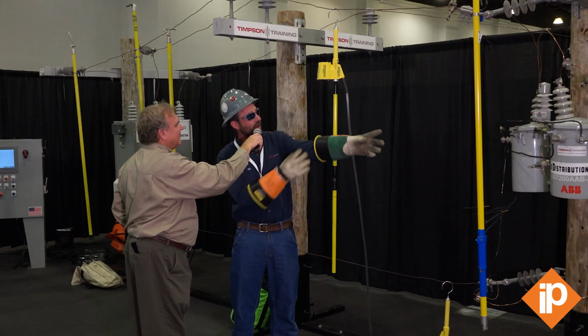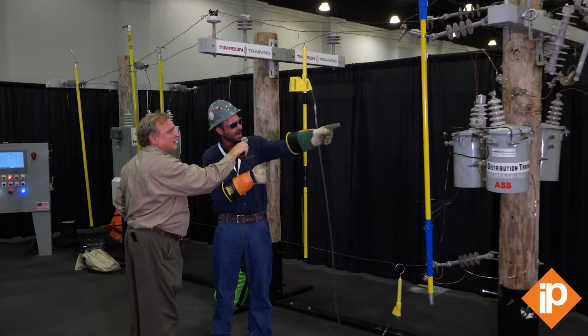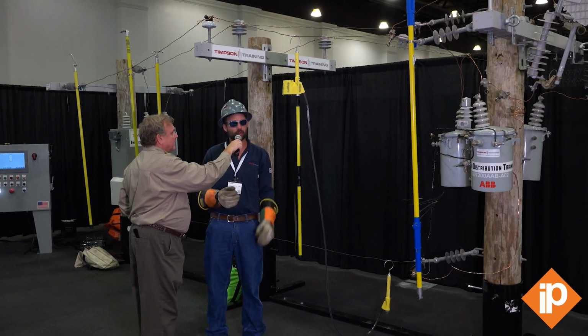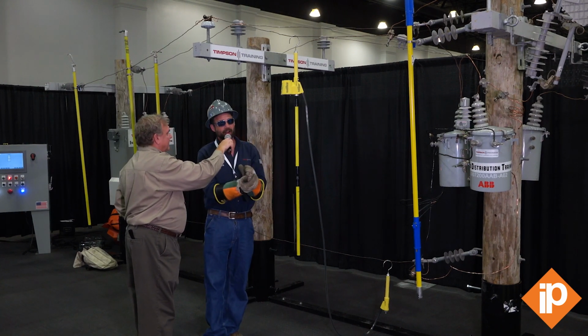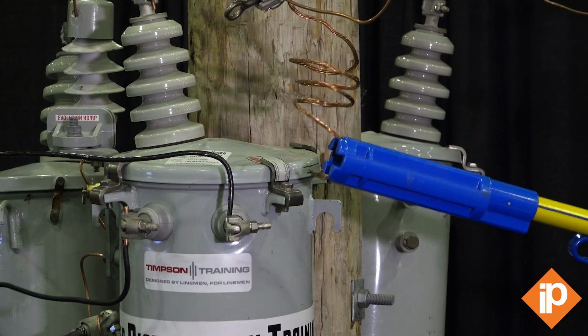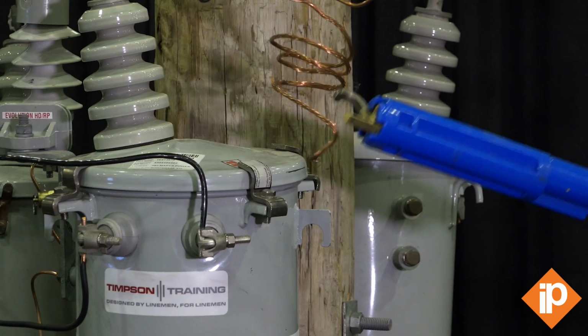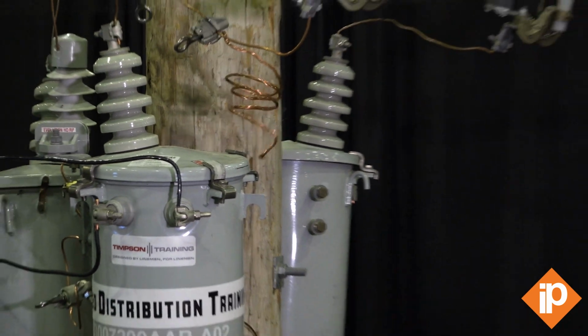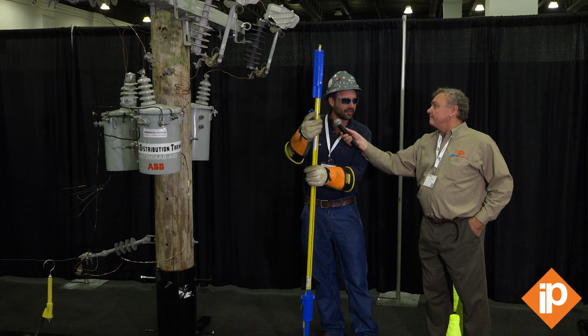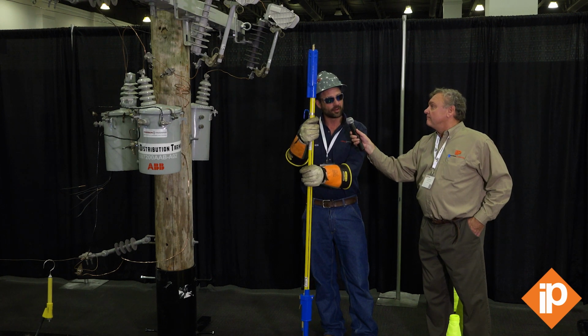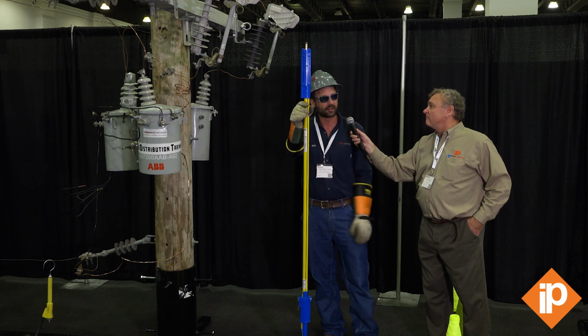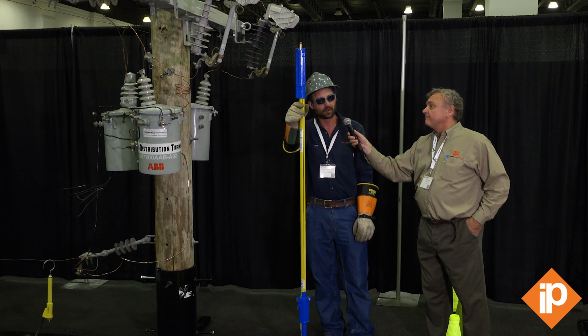So now that it's energized, I'm going to grab that tap and touch it to the case of the transformer so we can see what that primary arc looks like. Oh yeah, we saw a little bit of an arc there, right? The big thing about this is you're not going to have any arc flash whatsoever because of the high impedance transformers and how fast the relays operate.